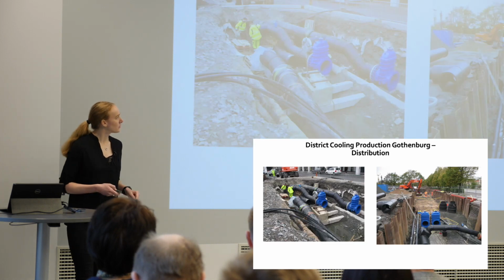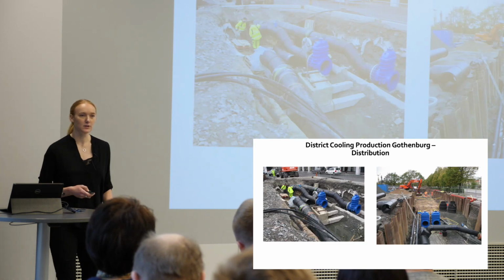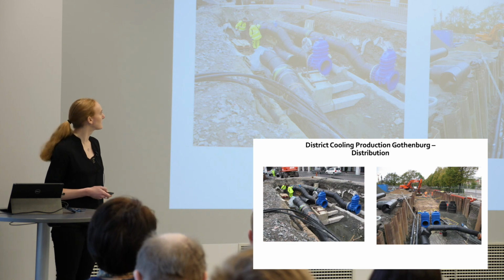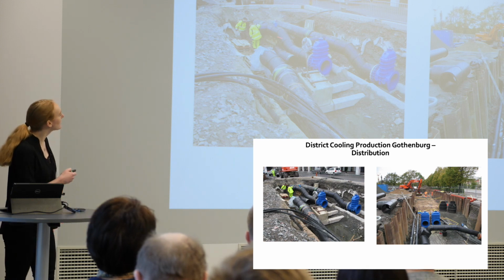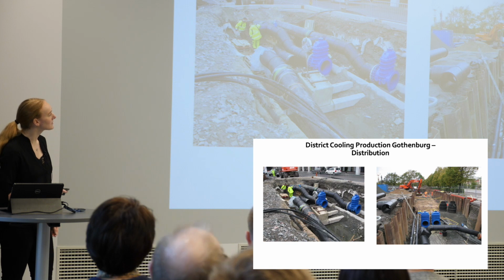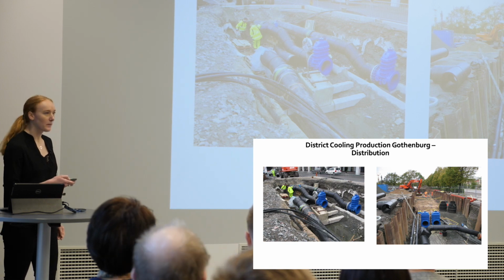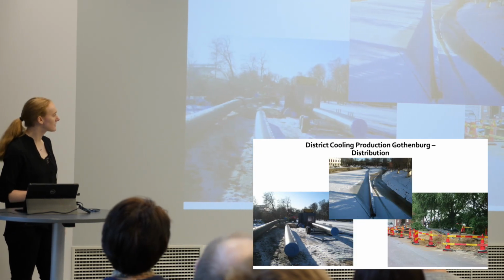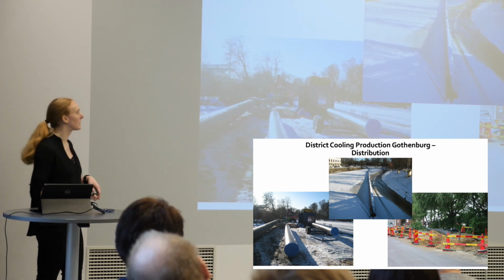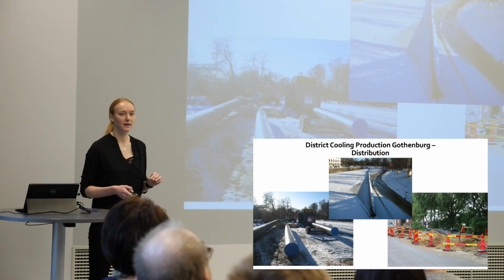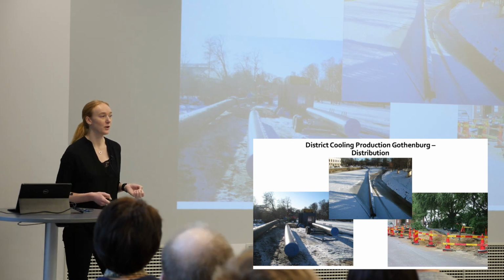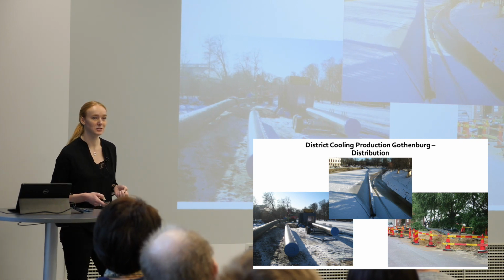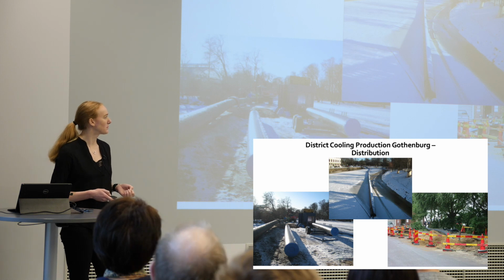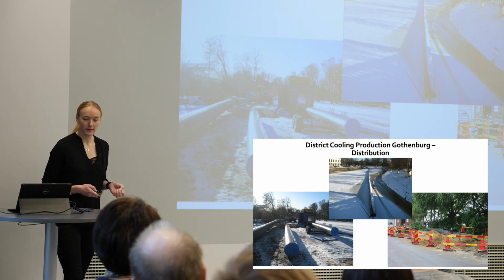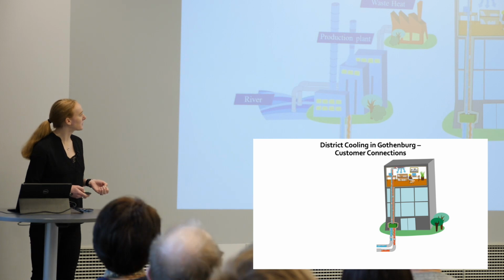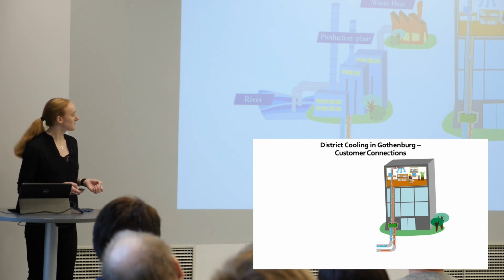And I just wanted to show you some pictures of how it looked when they were installing the pipes in parts of the city. You have these two guys here for reference of size. Compared to district heating, the pipes, valves, everything for district cooling is around 4 to 5 times larger because of the small delta T between supply and return. So larger pipes, more expensive. That was it about the distribution.